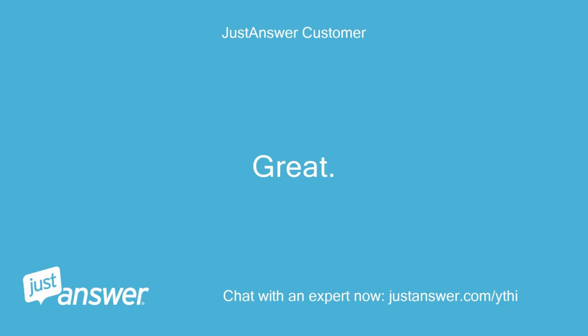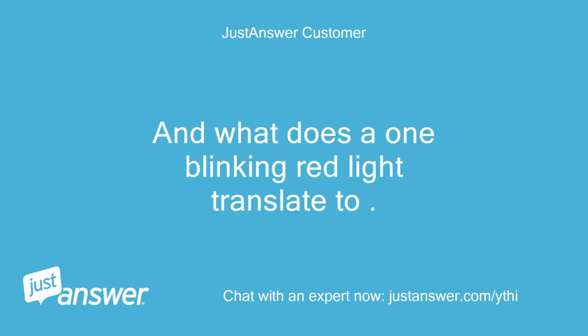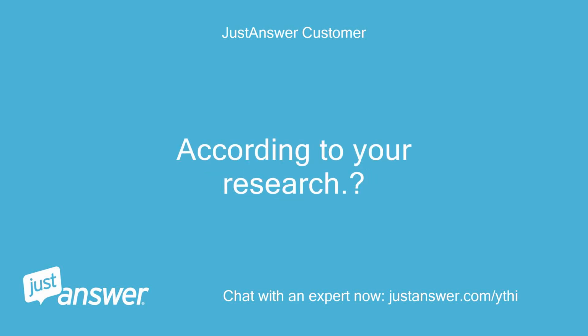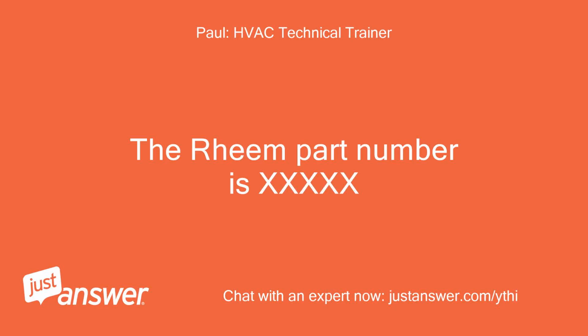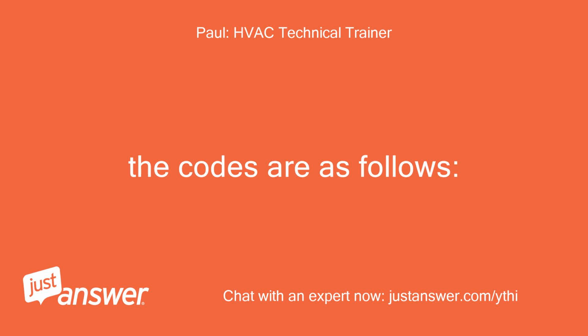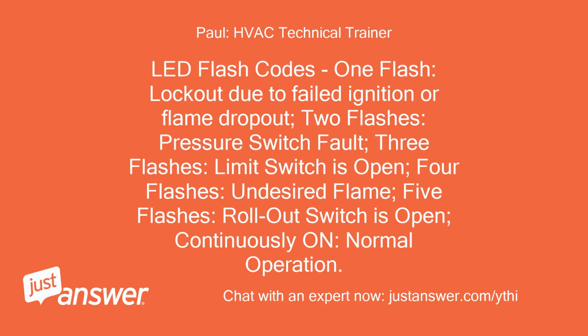Great. And what does a one blinking red light translate to, according to your research? The Rheem part number is XXXXX. The codes are as follows. LED flash codes: 1 flash, lockout due to failed ignition or flame dropout; 2 flashes, pressure switch fault; 3 flashes, limit switch is open; 4 flashes, undesired flame; 5 flashes, rollout switch is open; continuously on, normal operation.